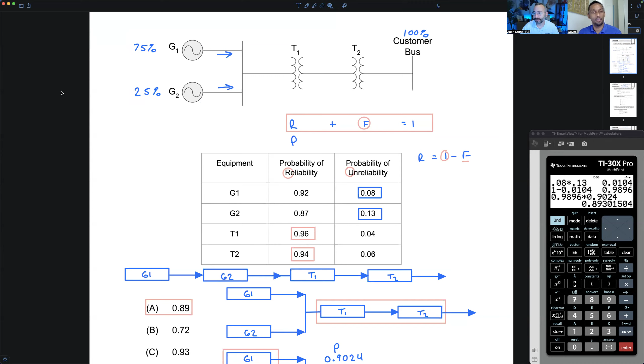Were you in class last night for day two of protection? Yes. Do you remember that example we did on load shedding with the frequency relay, where we had a plant generator? It was very similar, but the plant generator isn't big enough to supply all its own load, so it still imports a little bit from the utility. Yeah, that'd be a really realistic real world example of that. Okay.